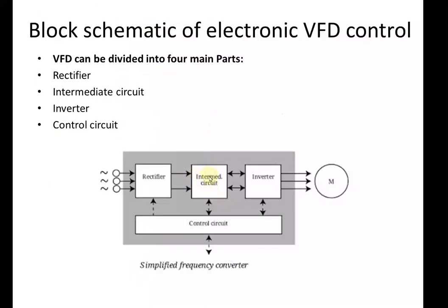The intermediate circuit is also called the DC bus or DC link — it sits between the rectifier and inverter. Since the output of the rectifier is DC and the input to the inverter is also DC, we use a DC link in order to avoid loss of DC current or voltage. It can also be seen as a storage facility from which the motor is able to draw its energy via the inverter. It can be built according to three different principles depending on the rectifier and inverter.